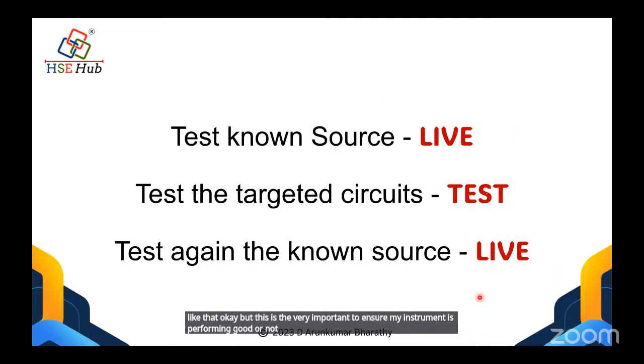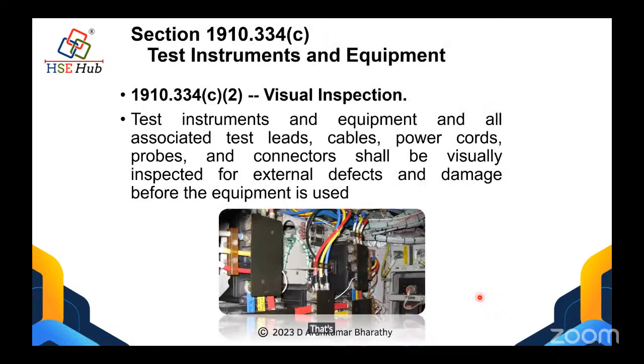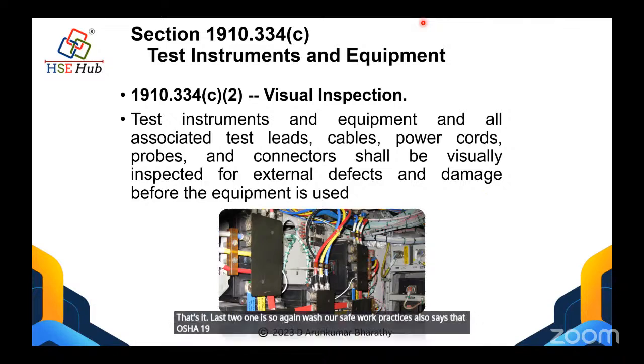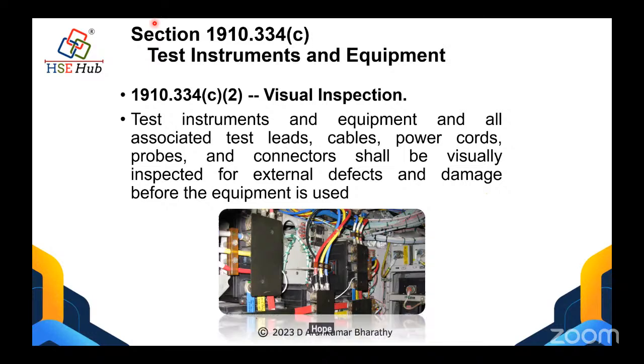Okay. Right. That's it. So the last one: OSHA safe work practices, OSHA 1910.334, says about test instruments and equipment that visual inspection is always regular. Test instruments, equipment, and all associated test leads, cables, power cords, probes, and connectors shall be visually inspected for external defect and damage before the equipment is used. So that visual inspection, and also the proper selection and proper usage of the instrument, will ensure the safety of the person. Hope you got some insight about test and measuring equipment safety and safe work practices.